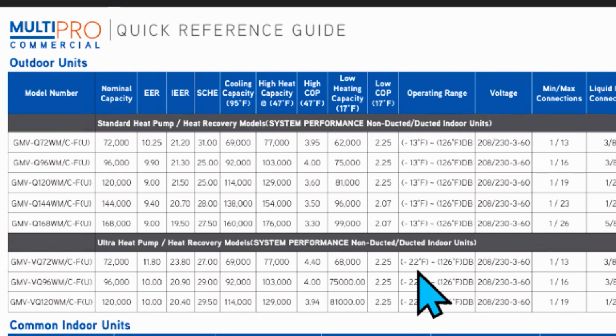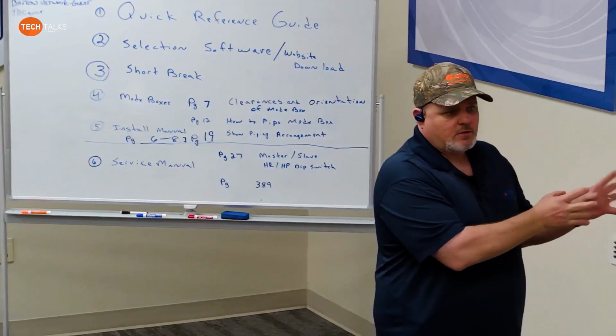These are built-in conditions set on the outdoor unit where you do not need to add any type of low ambient kit or any wind baffles to those units, where you see that on some of the other manufacturers out there. Well, there seems to be some misconception with some of that too, even in the mini split world, Flex, our MultiPRO units. We've had contractors ask, what kind of low ambient kit do I need? You don't need anything. Those units are rated for cooling without any additional information or additional products, put it that way. Correct. So you've got an inverter driven system. The compressor can speed up and slow down. They can also control the fan speed to keep the head pressure up when they need to. It's built into the machine. Yep.